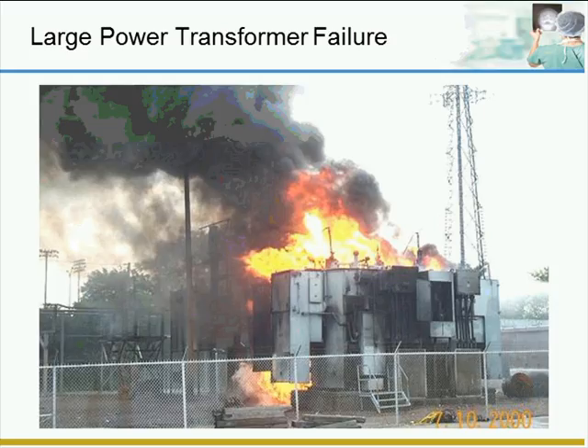This picture here is an electrical switchyard with a high-voltage transformer. There was an explosion from an internal arcing. The fire is oil, which is being burnt off. Typically, the oil will be internal to the transformer. Nothing should be catching on fire unless it's a severely bad condition. Larger transformers can take several weeks or months to obtain. A written contingency plan or redundancy, for example, the emergency generator, will minimize the downtime of the facility.